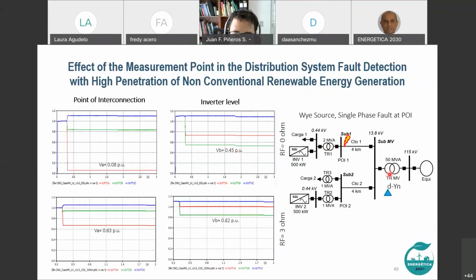In the case this transformer is in a wye connection, sorry, here it is delta, but it's a wye connection. If the fault is 0 ohms, okay, you can detect it, and if you have a setting, for example 0.8 per unit to trip, you can realize the voltage and the inverter will trip. But if you increase the fault resistance, to 3 ohms for example, then even if the system has a low voltage at the inverter level, you will not realize it if your setting is 0.8 per unit. Then it's very important, and we recommend, that you have a measurement point in the medium voltage network to realize the situation and trip the inverter at the right time, so that the inverter is not energizing that fault.